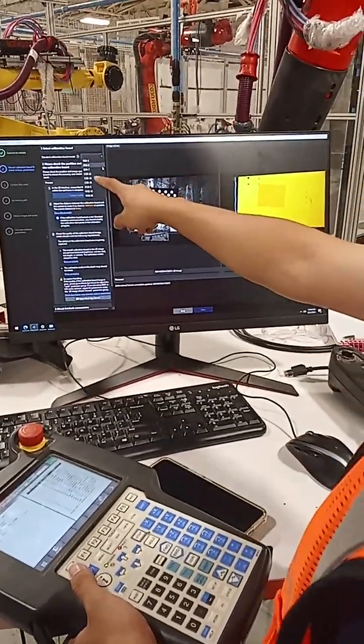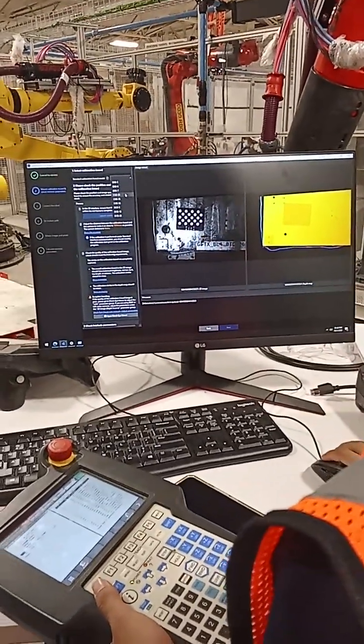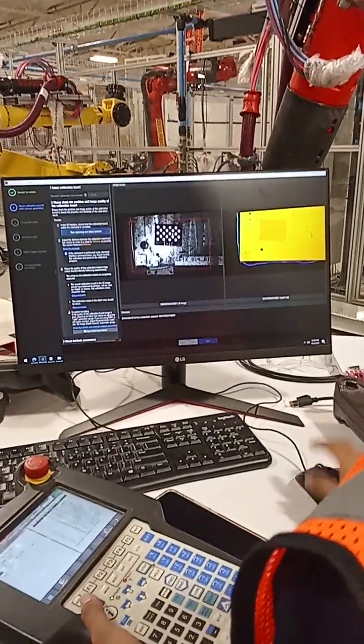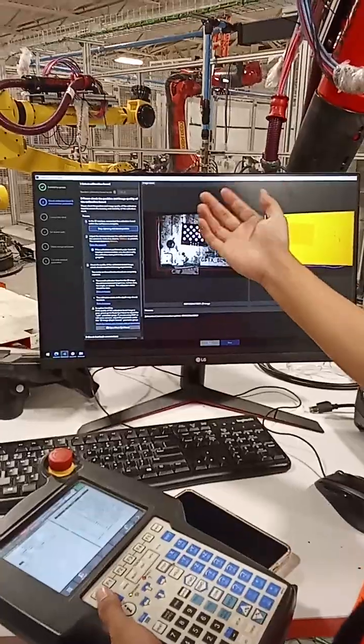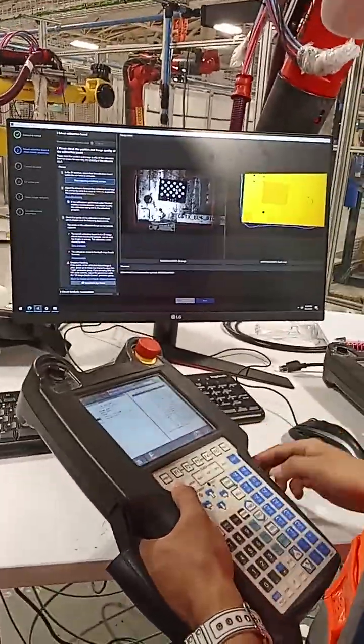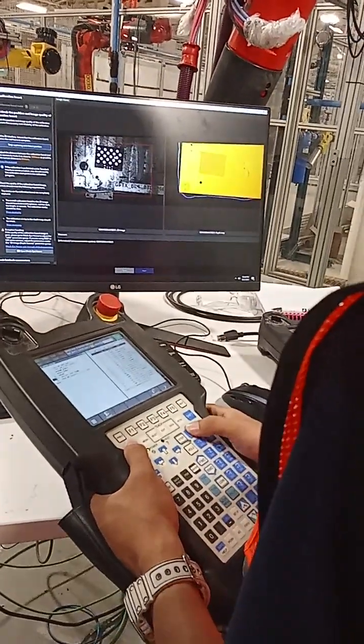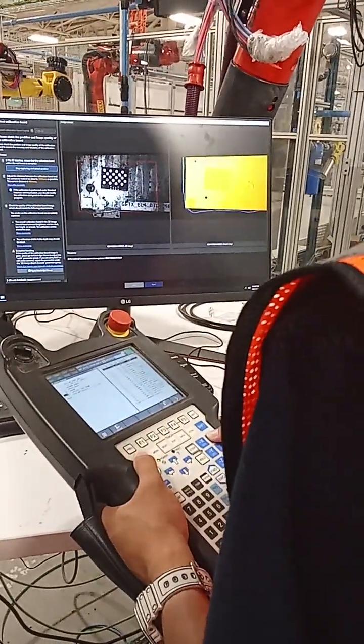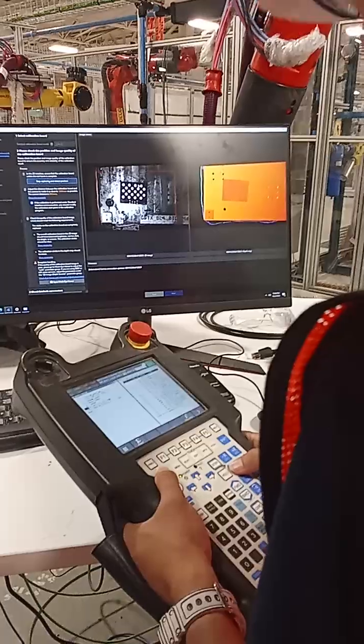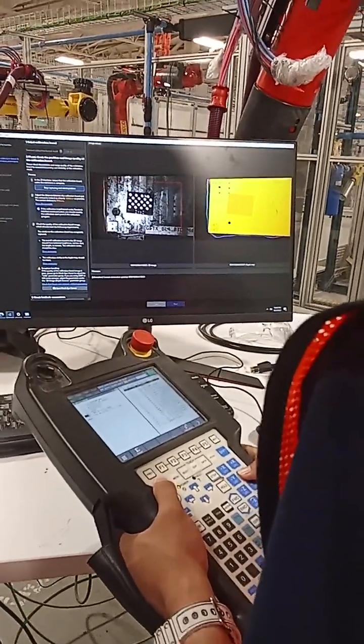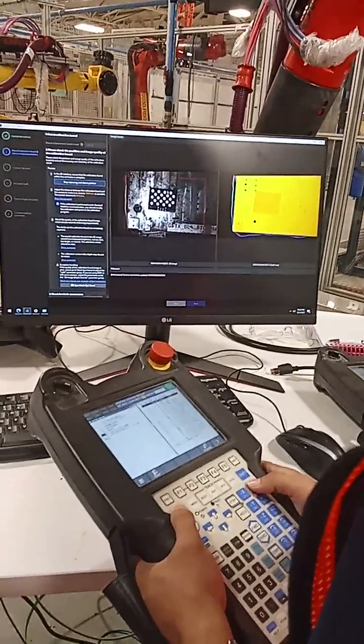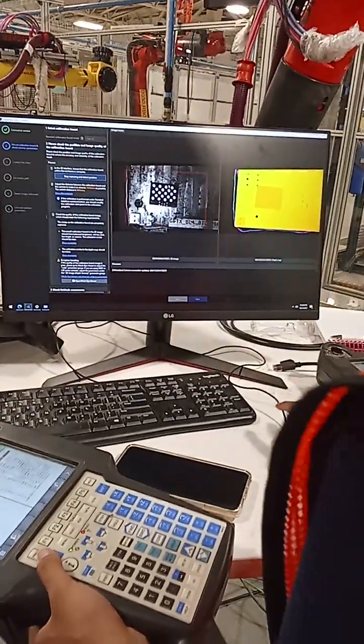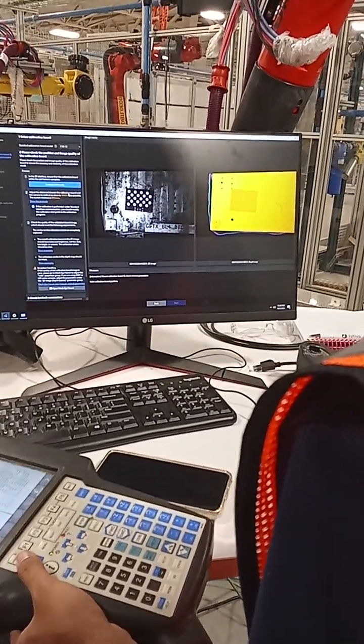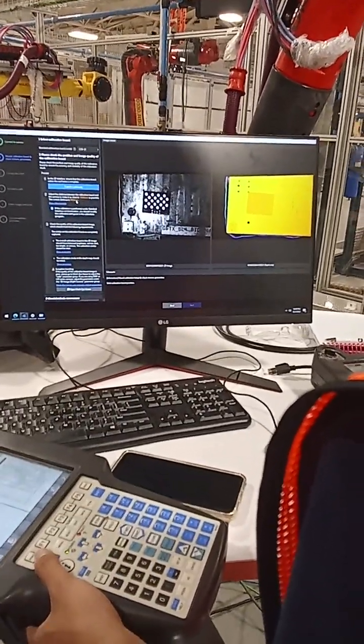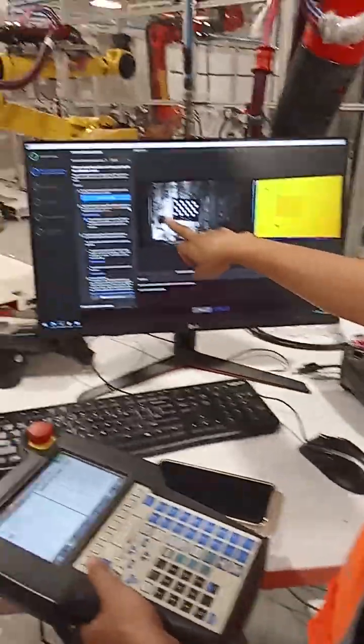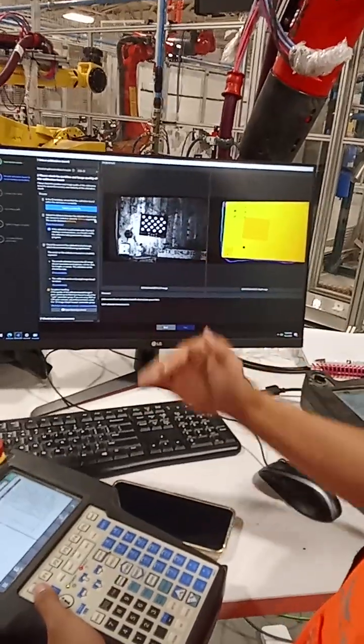So this is when it comes to selecting the board, depending on the name at the corner. This one is 20 right here. So we can do a continuous capture. We can make sure the board is pretty much at the center of the red box right here. If it's not, we can try to adjust it a little bit. It doesn't have to be perfect, just roughly at the center should be okay. And here is the recommended camera working distance. This is where we are right now. In general, we just set plus minus 250. That range will be okay to do calibration.